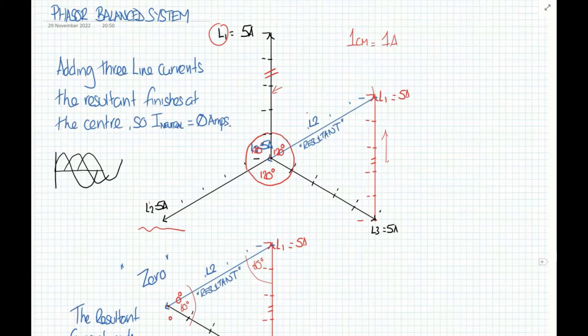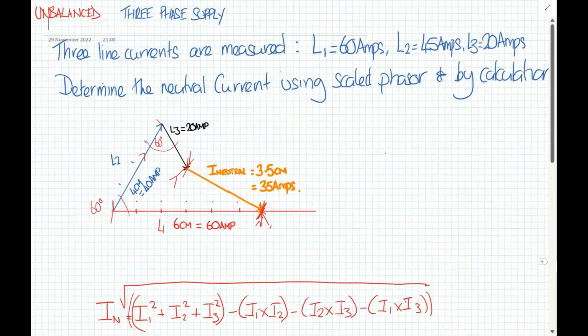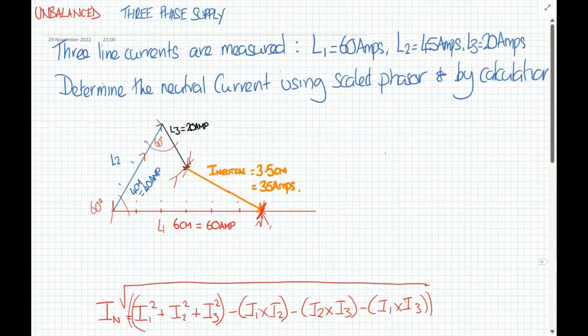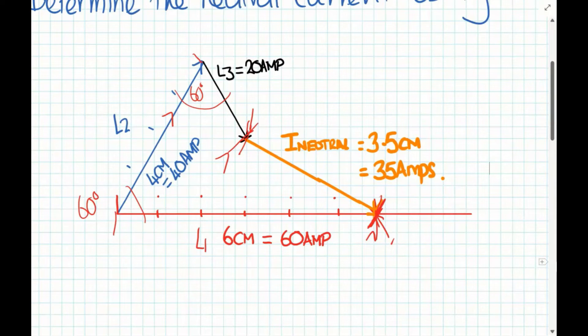What happens if we get a scenario where they're out of balance? If we look at an unbalanced three-phase supply, this time we've got L1 at 60, L2 at 45 and L3 at 20. Determine the neutral current using a scaled phasor. We'll start with the phasor first. The first line current L1, 60 amps or six centimeters. We draw six centimeters to the end here. We then add L2 at 60 degrees. There's our 60 degree angle and L2 is 4 centimeters, that's 40 amps. At the end of L2 we add L3 which is two centimeters, 20 amps at 60 degrees to there.